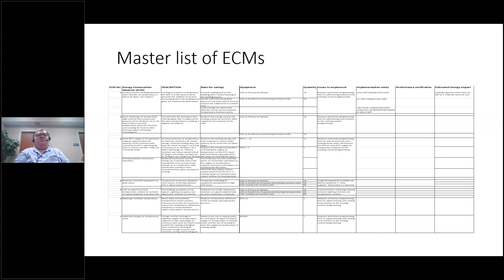Now, we want to be creative, okay? But one of the keys you need to focus on is matching your capacity to your load. That's the most efficient operation: use the minimum amount of energy to accomplish whatever you're trying to do. You find the most efficient point of operation across the system's range of operation. How much GPM can I pump and still keep the equipment online? That's a combination of whether the pump will work at that point, and whether the chiller, or boiler, or whatever it's providing water to, will accept that. Can I operate in that range? You can take multiple steps, there are multiple things you can do, and that's kind of what the illustration says: one big ball on one side and three small ones on the other, but it balances out, matching capacity to load by implementing this balancing act.